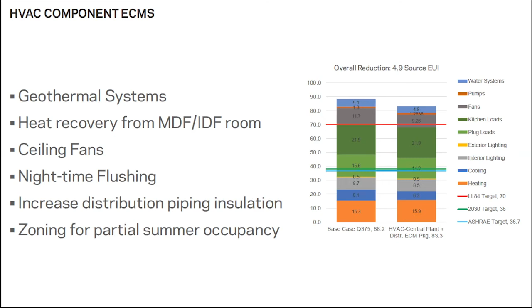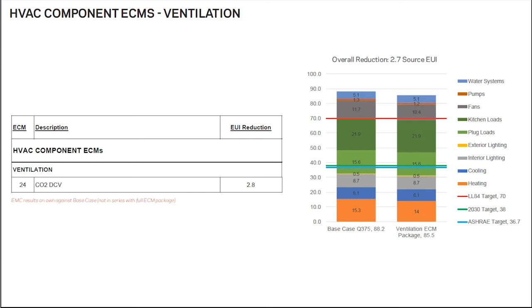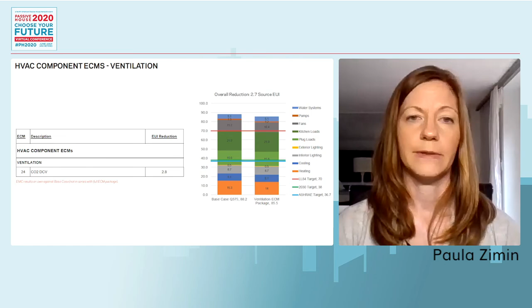Related to ventilation, I mentioned as we started out that the RTUs deliver air to classrooms, and outdoor air is controlled by occupancy sensors. That was in the old SCA standard. Just by switching over to a CO2 controlled DCV, we could see significant savings, and that just helps you understand that maybe there's 2 or 3 people in a space, which an occupancy sensor would trigger for full ventilation as if the classroom were fully occupied, whereas a CO2 sensor may say, there might be 3 people in this room, but there's not enough CO2 buildup for me to provide full fresh air. So there could be more variation in airflow.